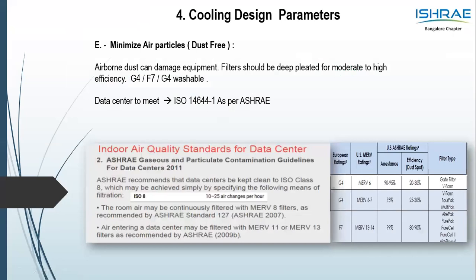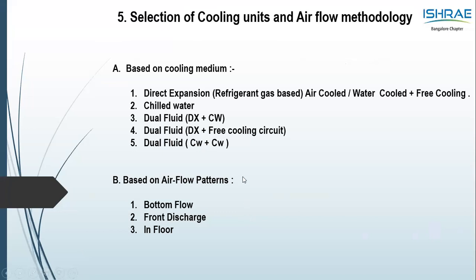So touching on the dust-free environment, as I said, most of these cooling units are placed in a close control room where pressure is not taken. Thereby, the filter which is going into the CC unit would be a MERV 8 as per ASHRAE 2011. If at all there is a fresh air or outside air entering the data center, the filter to be upgraded to a MERV 11 or 13. So this is on the check on the filter which goes into it.